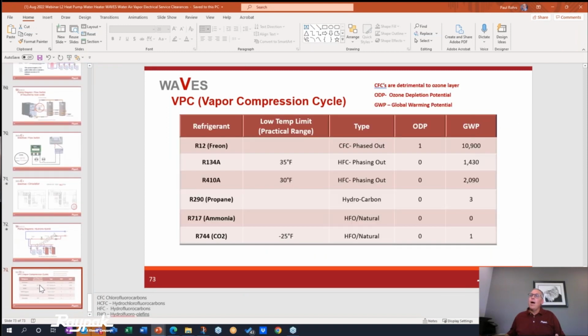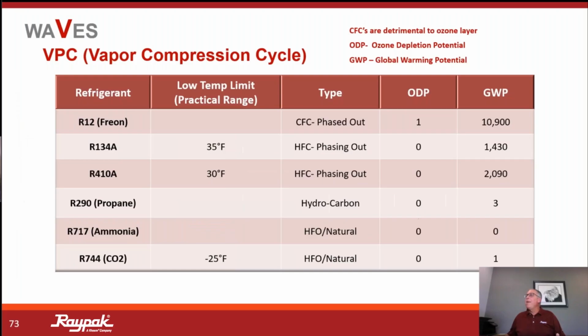41. I will say this for future reference. I'm going to go back here. So I've been doing some due diligence on the different refrigerants that are being used. And what was being discussed is if you go back in time, decades ago, maybe they had Freon systems. Well, those CFCs, chlorofluorocarbons, have been phased out. That's why you no longer can use Freon, right? There is an ozone depletion potential that's looked at, a global warming potential that's looked at.